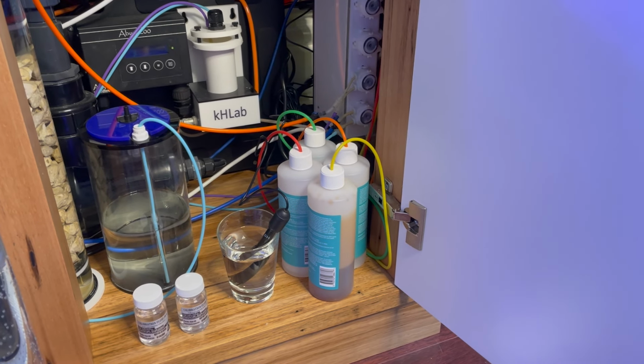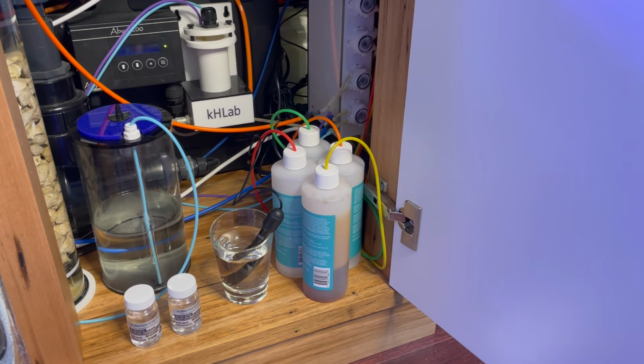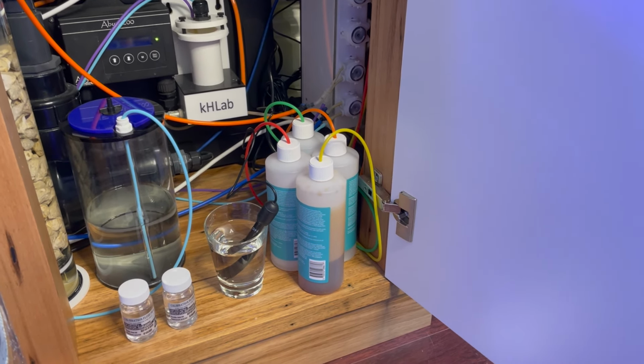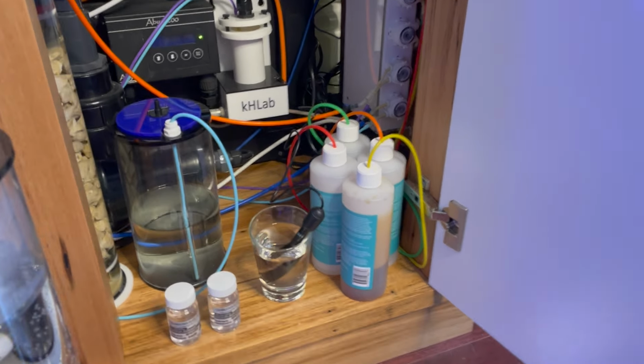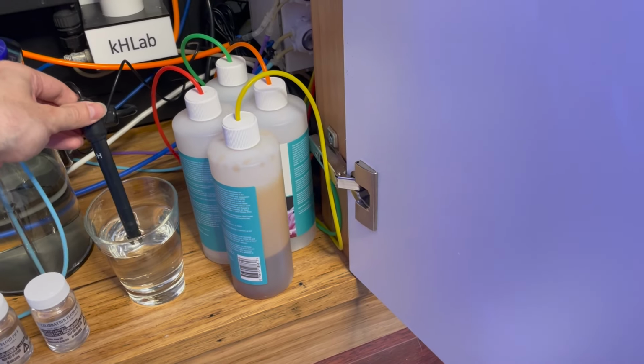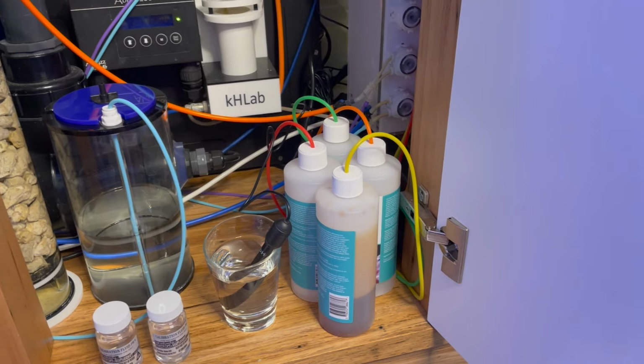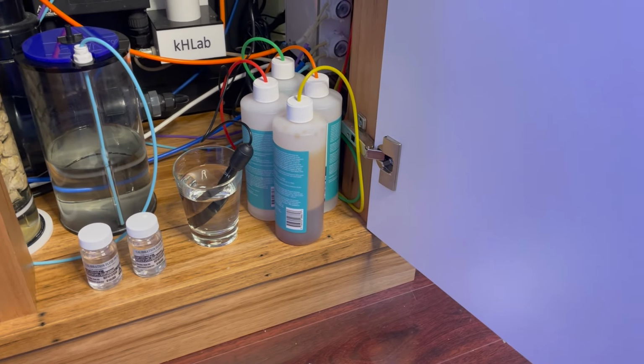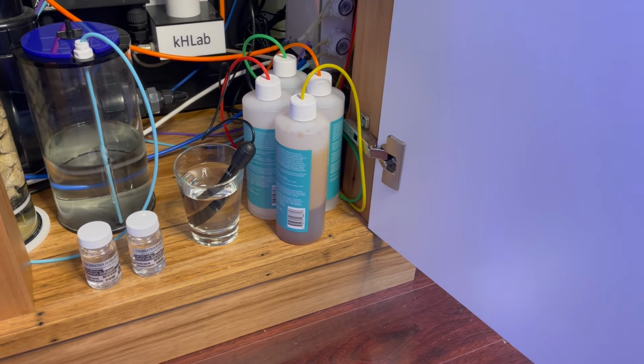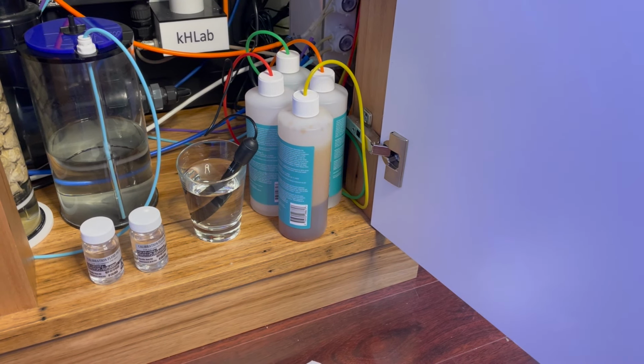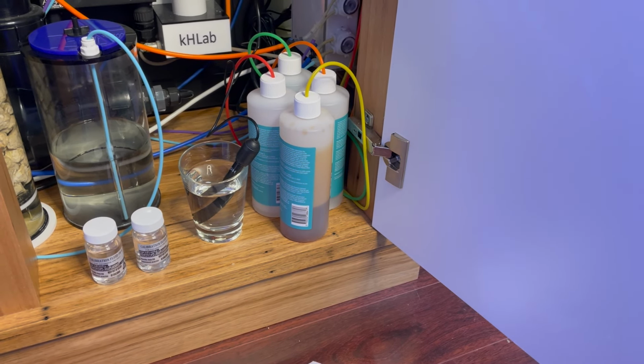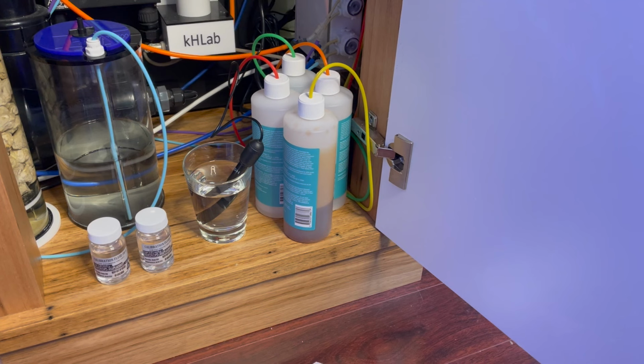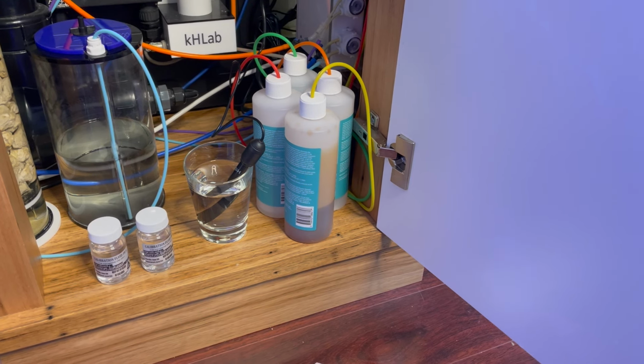Alright, in this section I'm going to show you how to calibrate the pH probes on the KHLab. So there's a couple of things you'll need. First is your pH probe, and I have it sitting in a glass of RO water. When using a brand new pH probe, it is good practice to just let the pH probe rest in RO water for 10 or 15 minutes after unpacking it and unboxing it.